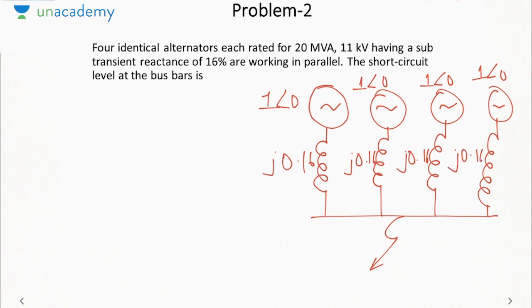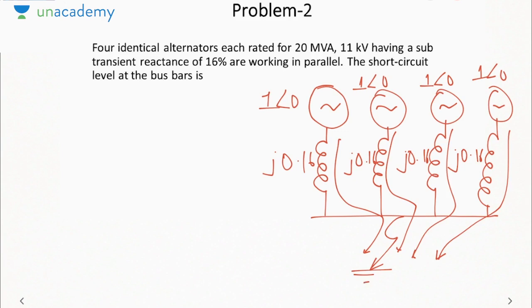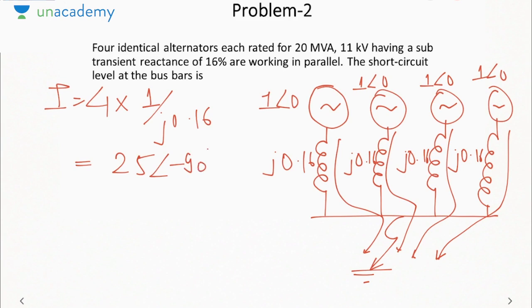Now when you wish to calculate the current, as I told you, every machine will try to deliver current into the fault. So how will the current flow? Like this, from here and here. Since this is short circuited, this is grounded. So the current will be 4 times the individual current. Individual impedance is j0.16, so it will be j0.04. So 1 by 0.04 is 25 angle minus 90 degree pu.